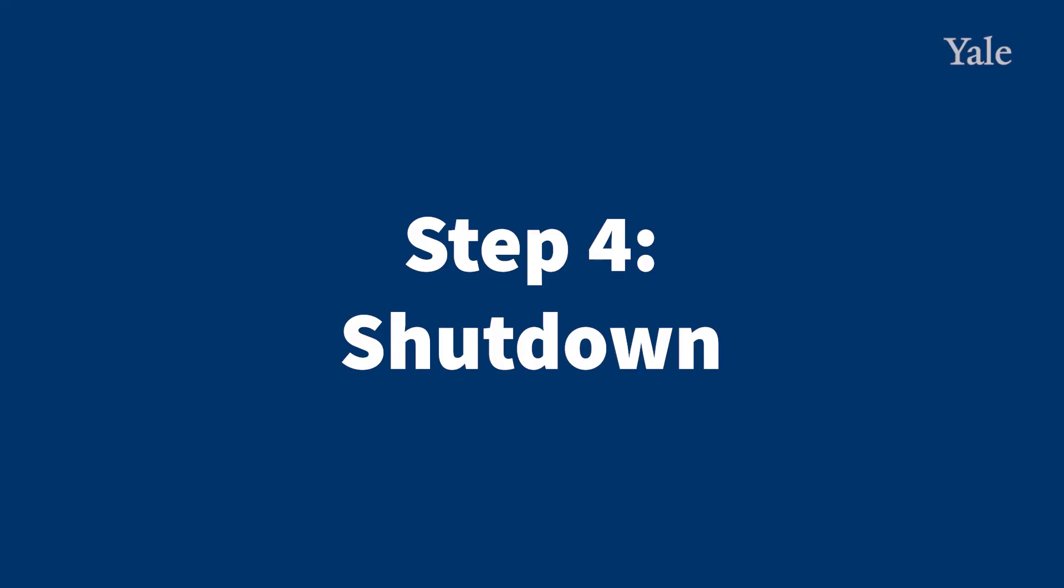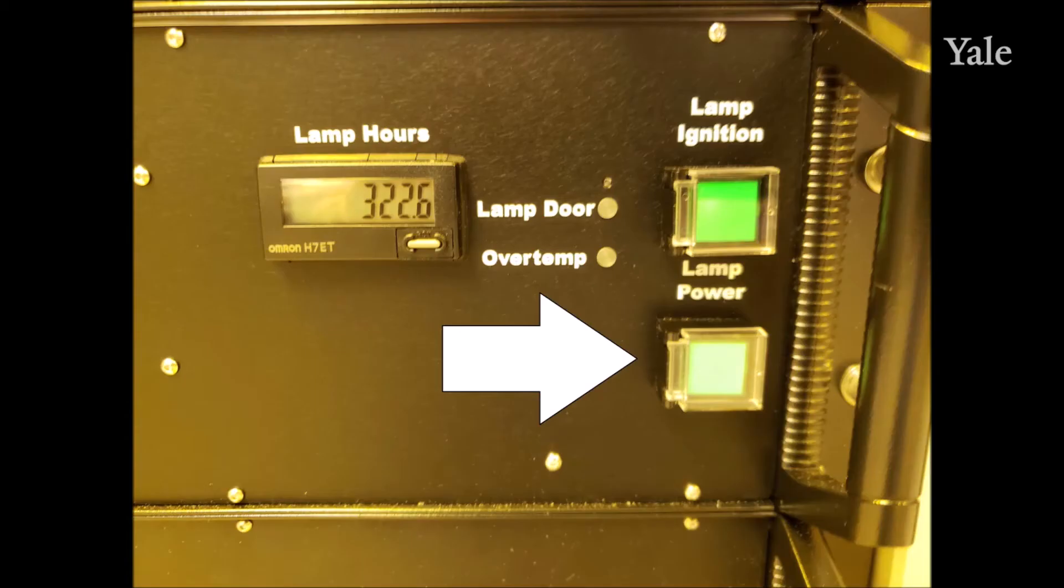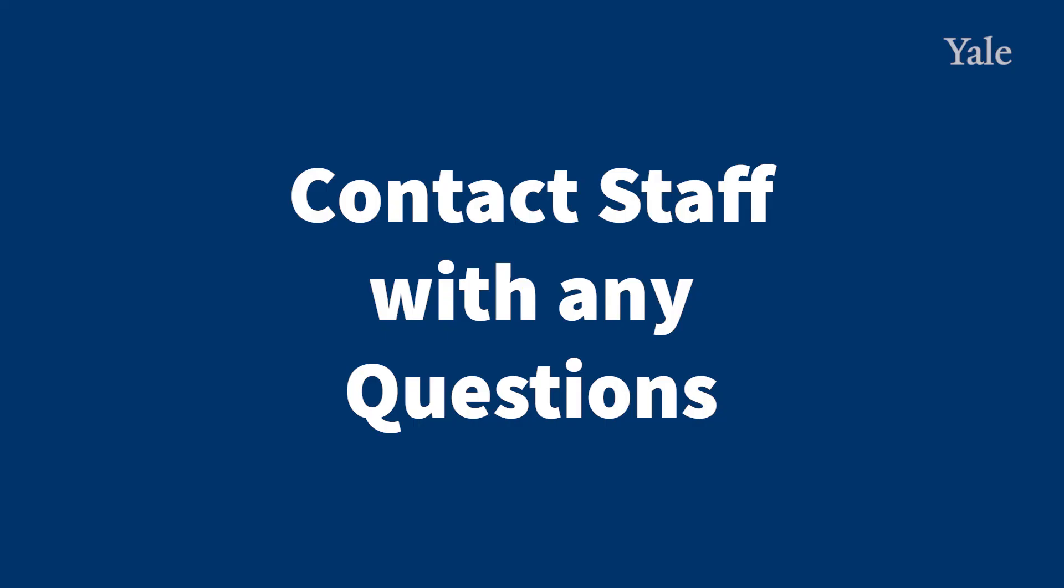Step 4: Shutting down the ellipsometer. After removing your sample, press the Lamp Power button to turn off the lamp. Please contact a staff member with any further questions. Thank you.